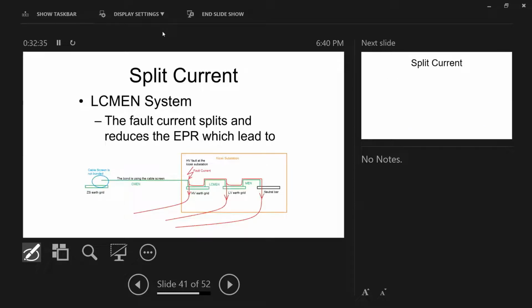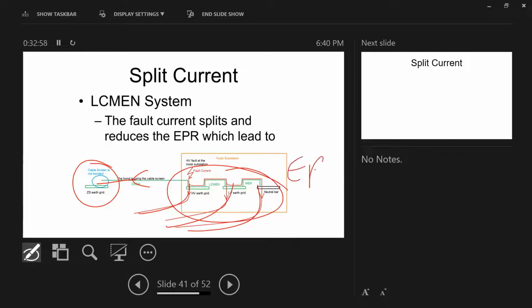The fault current will split only into the ground because it's open at the end. See this? Because it's open, I must have a closed loop for the current to flow. If it's open, the current will not flow back through here. All of it will go through this and cause me an EPR in here.